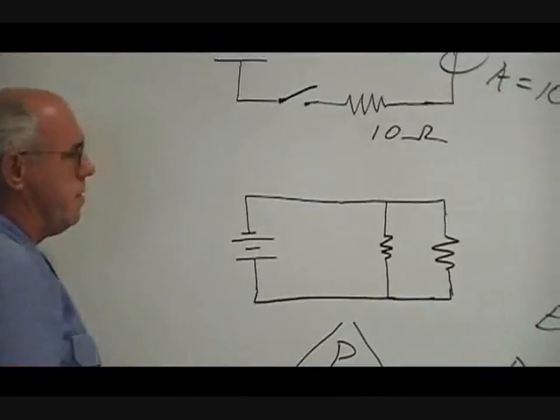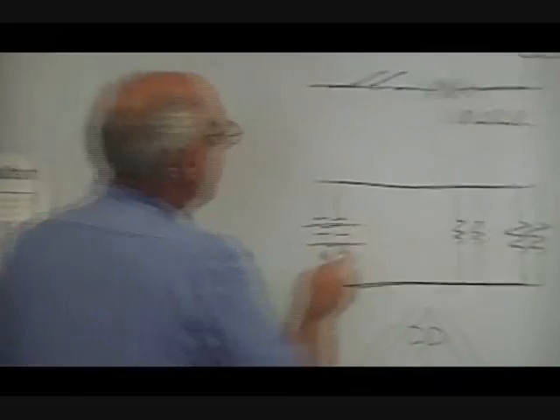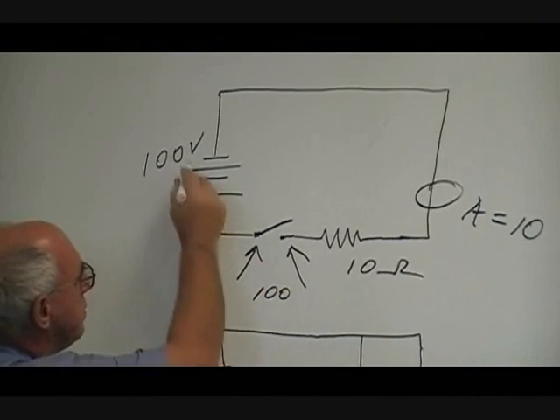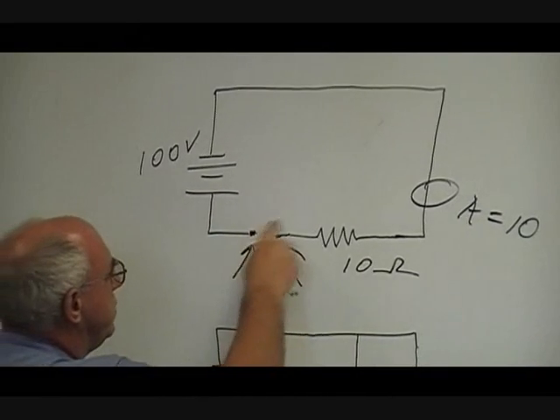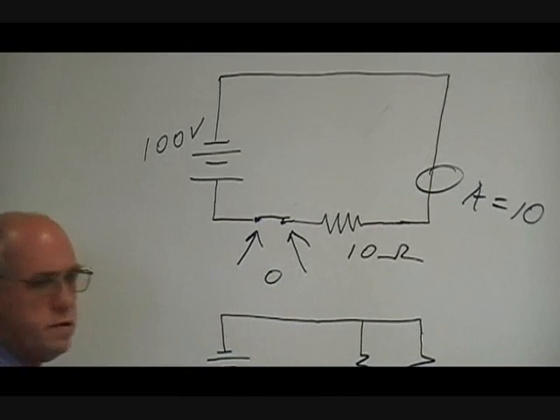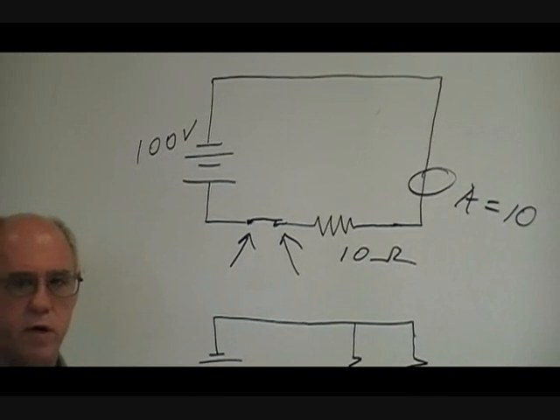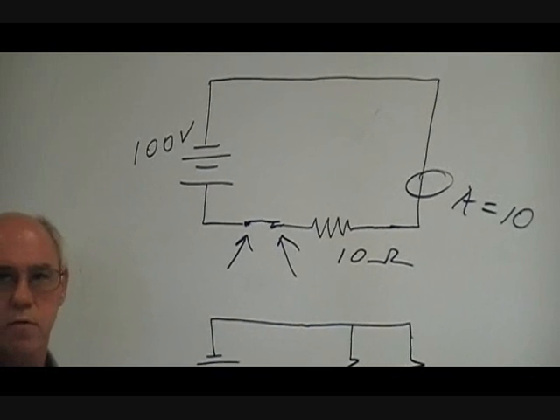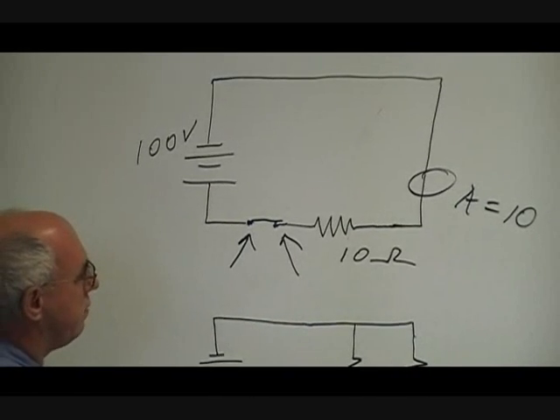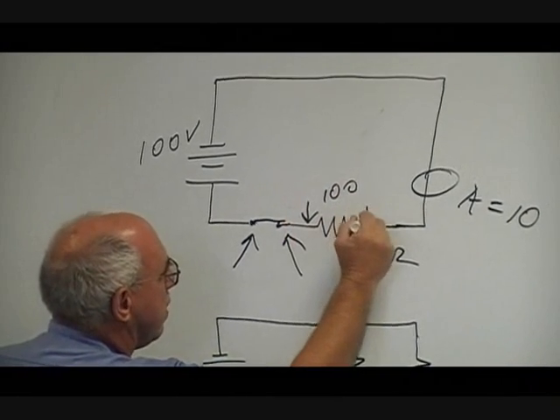Now let's talk about voltage drop, because when you troubleshoot you're looking at voltage drops. If this switch is open and I put a meter across this switch, it is going to read the source, 100 volts. If this switch is closed and I put that meter across there, there is no voltage drop across here, so it's going to read zero volts. That may not make a whole lot of sense, but a switch is just like a piece of wire. When it's closed, it should have very little resistance. Therefore it would have no voltage drop across it. If I want to see what the voltage drop across this one resistor would be when the circuit's operating correctly, I can go back to Ohm's Law, take my current times my resistance, and I would find that the 100 volts would be across this resistor.